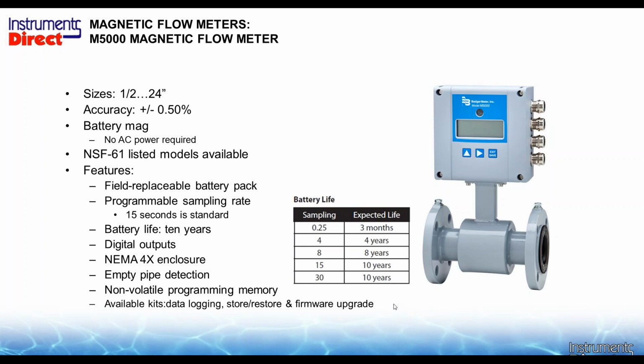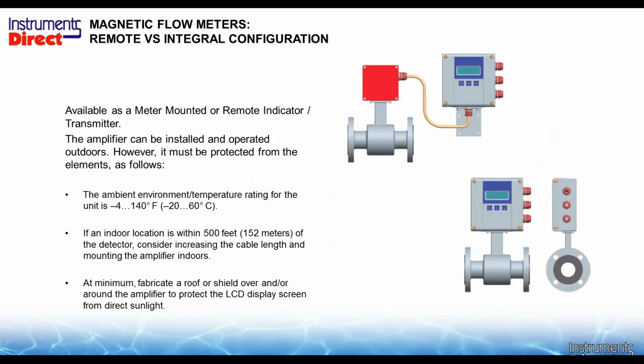Moving on to the battery-powered side, it looks basically the same as the AC-powered side. It's only available from 1/2 inch to 24 inches. Accuracy is now down to 0.5%, because it doesn't sample as fast as the AC-powered version, and you have choices of programming the sampling rate based upon the life expectancy of your battery. If you have it take a sample every 15 seconds, the battery is going to last 10 years, which is longer than the lifespan of most flow meters, so I wouldn't worry about that. Digital outputs, NEMA 4 enclosure, empty pipe detection, and again, logging kits are available too, especially with battery applications. The reason you're running off a battery is you don't have any wires, so if you need to collect information, the data logging function might be very advantageous.